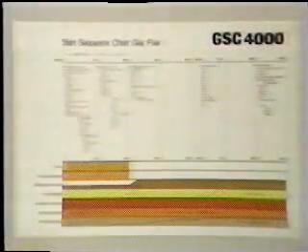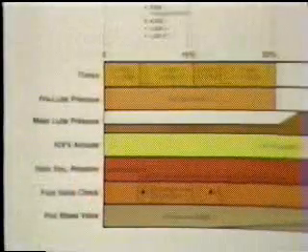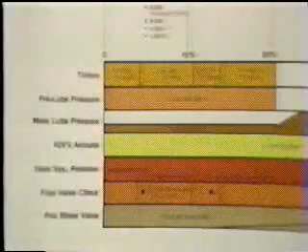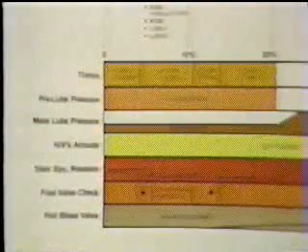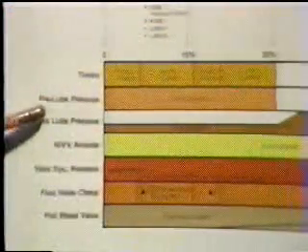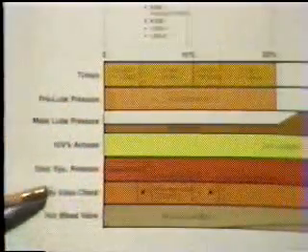Now, we can use the start sequence chart to isolate a fault if we know the time and speed at which the fault occurred. If the engine shuts down at 15% speed plus 5 seconds, we can isolate the probable causes. We begin by determining what conditions need to be met at 15% speed for the engine to continue the start sequence. By looking at the mechanical events, we find that pre-lube pressure must be 41 kPa. The starter must be on, and both fuel valves must be closed. Our first step is to verify that each of these conditions was met.